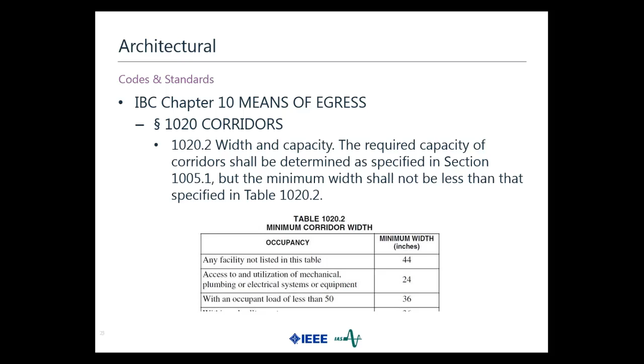When I was looking at this, I actually went to the NEC handbook 2017 and looked at the pictures they've got for large switchgear, the 1200 amp switchgear. I could not find anything in the informational notes or explanatory material in the handbook that actually gave the required width around it for your escape path.